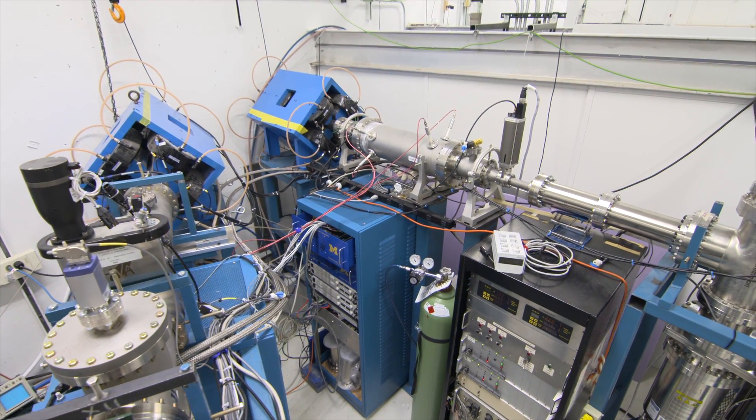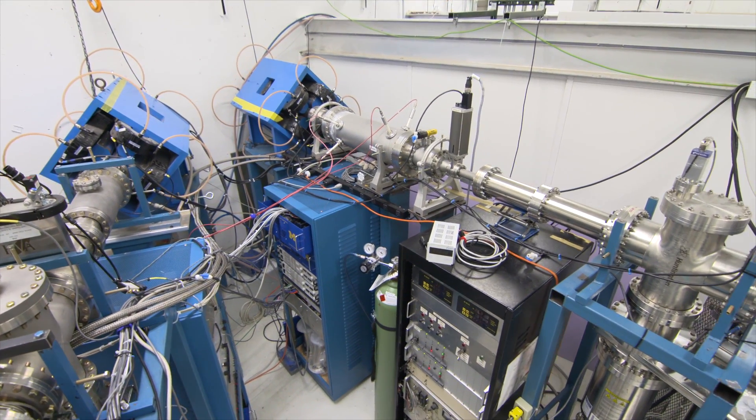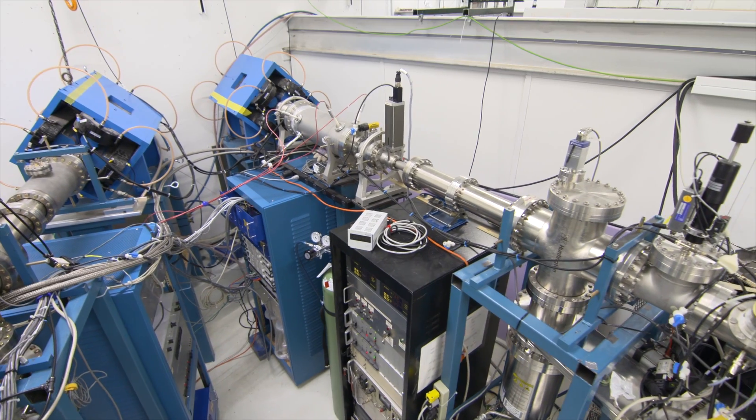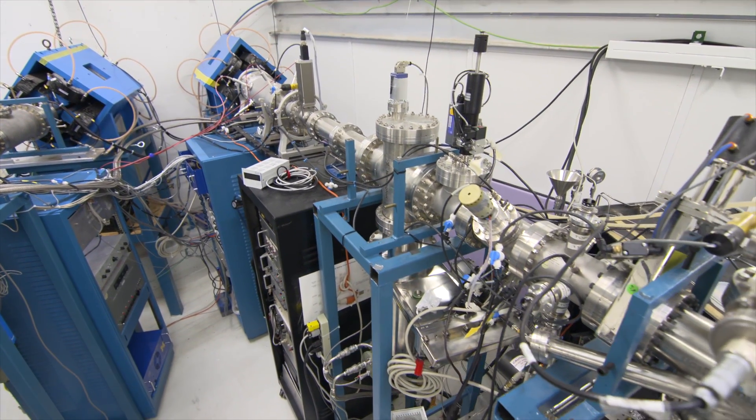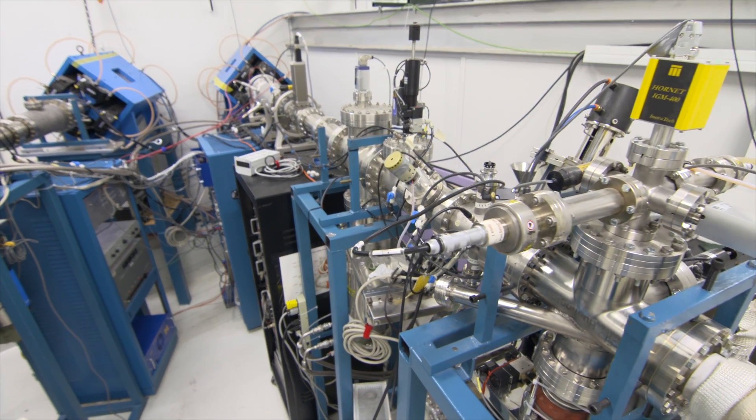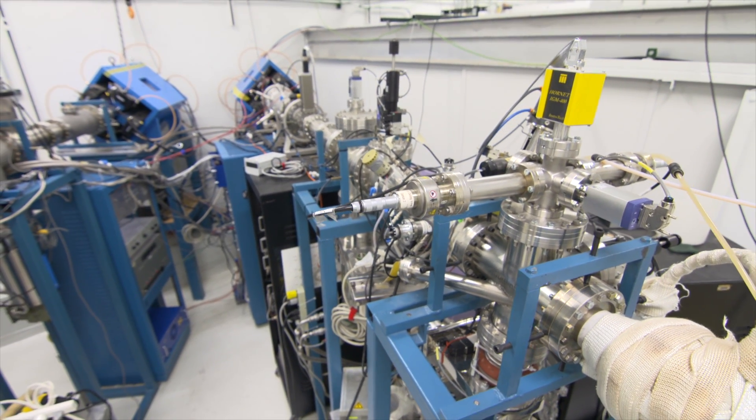The IAC chamber on beamline 3 is coupled to a high-temperature, high-pressure water loop capable of supplying flowing water at a temperature of up to 320 degrees C to a corrosion cell to conduct irradiation-accelerated corrosion experiments.